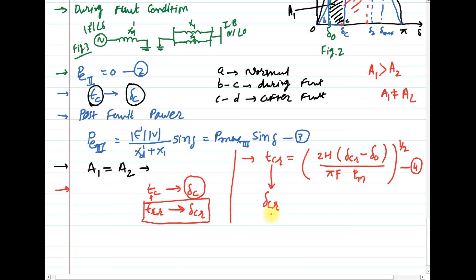Here there is no need for a full derivation of this equation, that means the critical clearing time. At critical clearing time we will get an angle delta CR, which is the critical clearing angle, and if we clear the fault at an angle of delta CR, then this condition is always fulfilled, that means the condition of stability is always fulfilled. Clear?